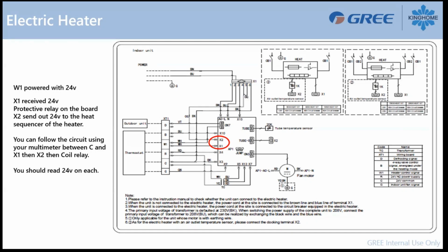But basically, if you take your multimeter and you try to follow the 24 volt power from the thermostat, you will send out 24 volts when a command for your duct heater is sent. And you can follow your 24 volts here on X1. If you don't have anything on X2, that's because your blower motor doesn't have the feedback on the board.